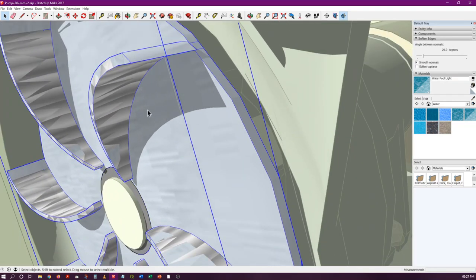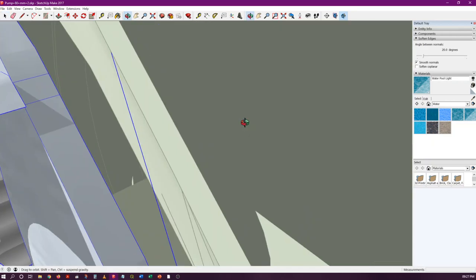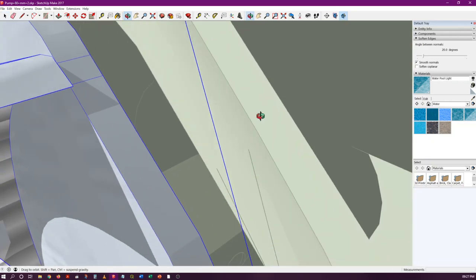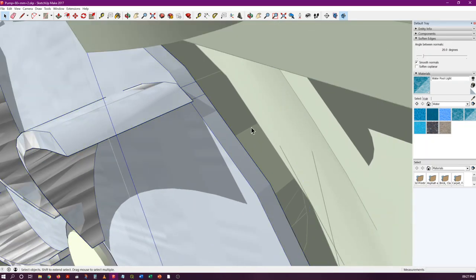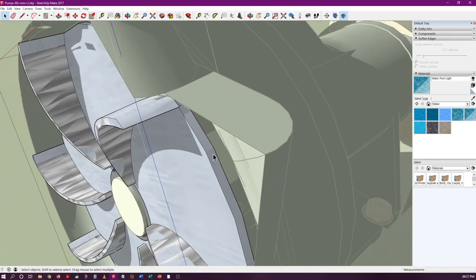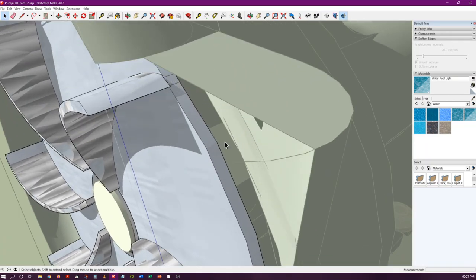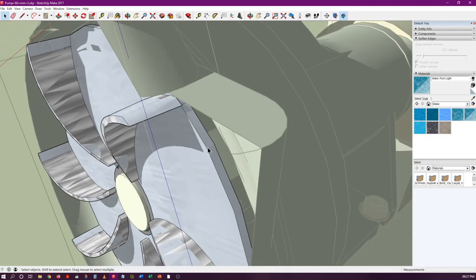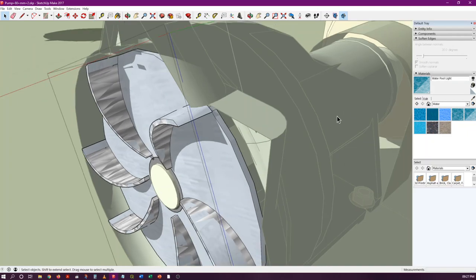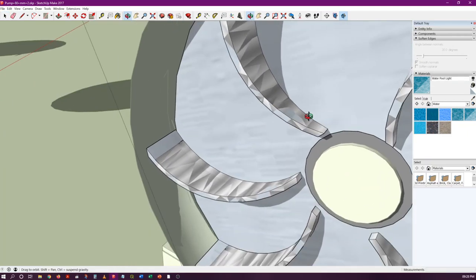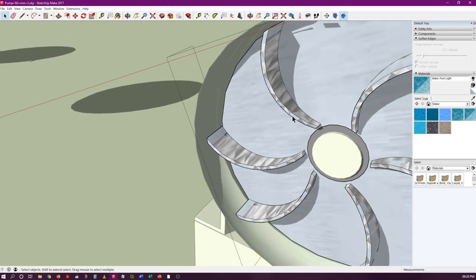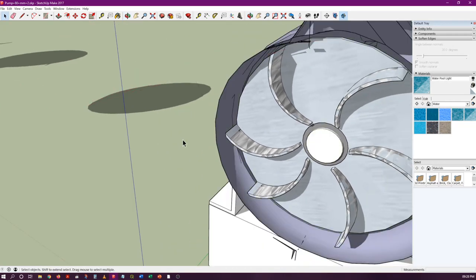That means this portion behind this shroud or plate will be kind of a cause of inefficiency of the pump, because this water cannot be rotated as efficiently. It will have some minor rotation, but not at the speed required. It's kind of a dead zone that causes some amount of inefficiency.